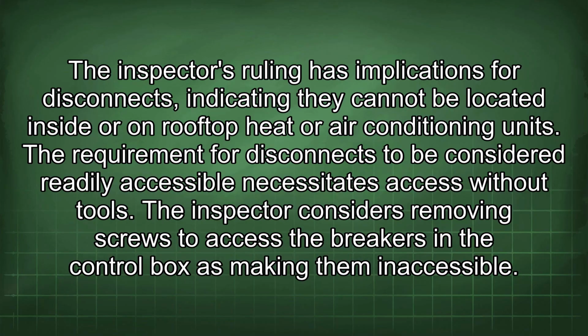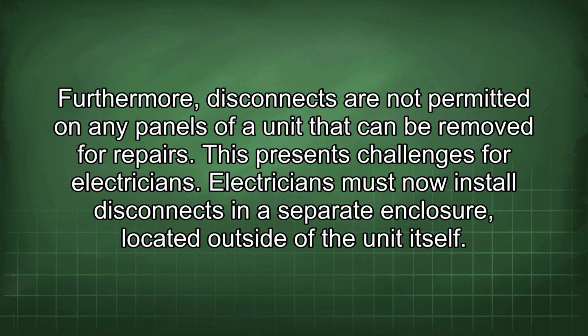The inspector's ruling has implications for disconnects, indicating they cannot be located inside or on rooftop heat or air conditioning units. The requirement for disconnects to be considered readily accessible necessitates access without tools. The inspector considers removing screws to access the breakers in the control box as making them inaccessible. Furthermore, disconnects are not permitted on any panels of a unit that can be removed for repairs.